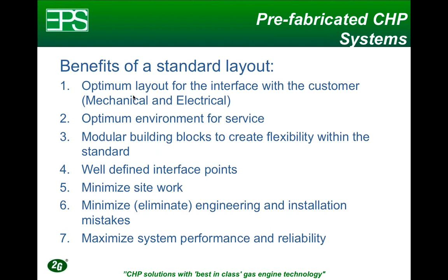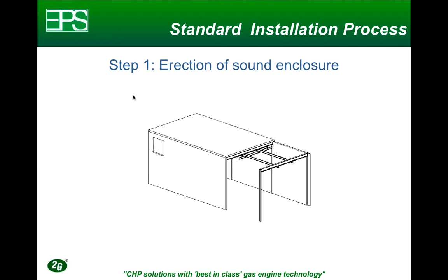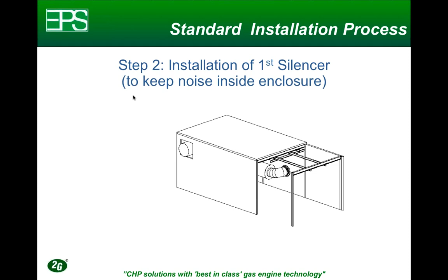So if we work with these standard products, this is how we would build up a cogeneration system like this. We would start with the assembly of the sound enclosure. Then once the enclosure is assembled, we start mounting the first exhaust silencer, done to keep noise inside the enclosure.